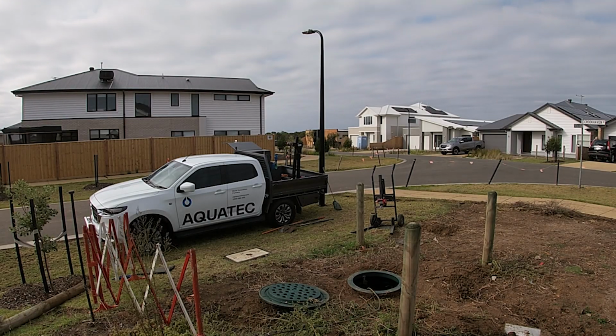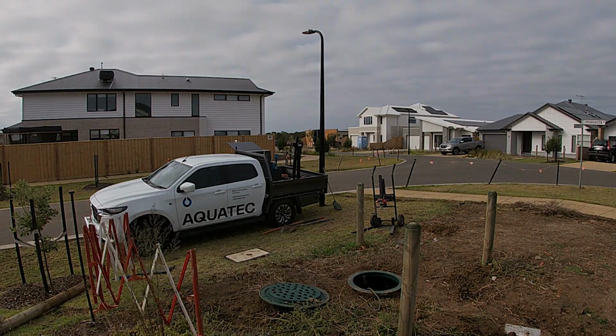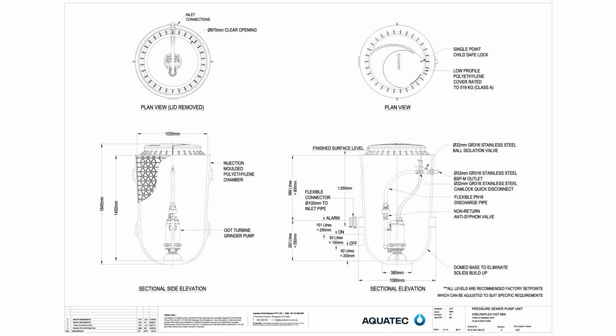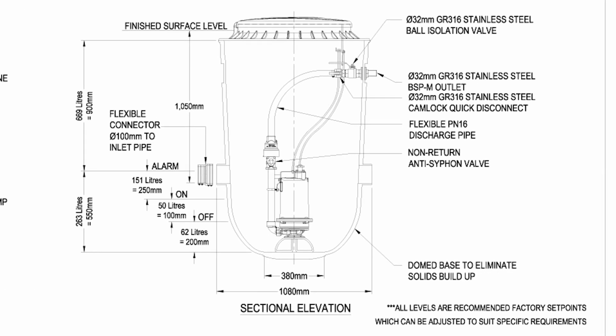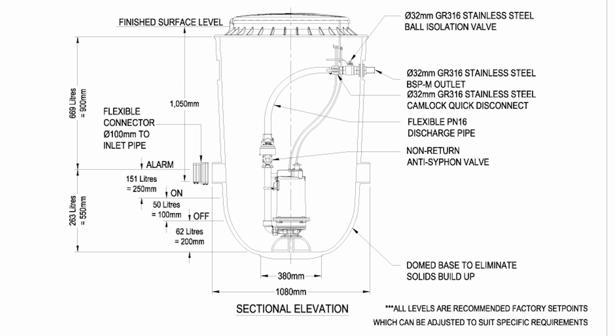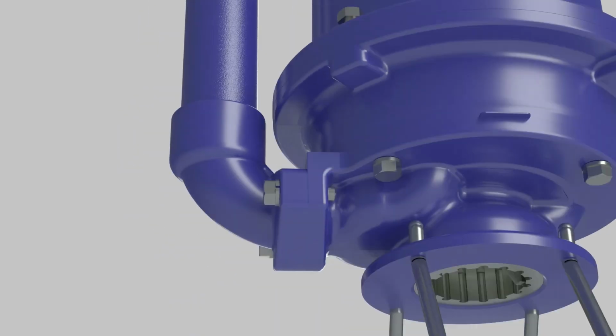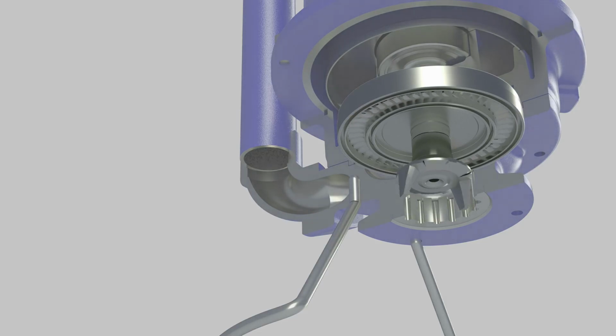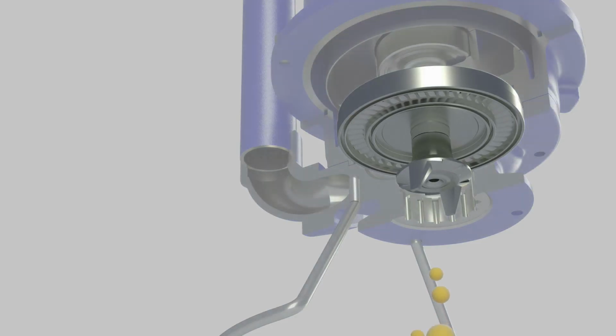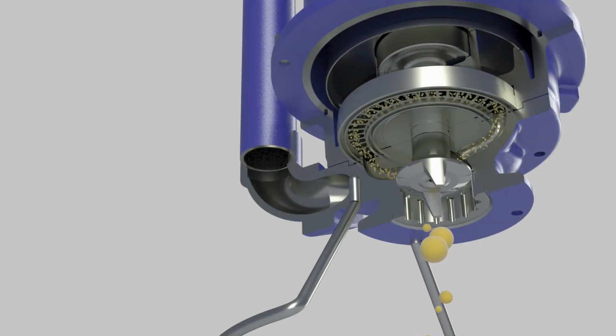Continue to pump the system out until it gets to its off level. The off level should be verified back to the system drawings showing the operational levels. Typically, this is between 200 and 250 millimeters of liquid left in the bottom of the well. In any case, it should always cover the wet end of the pump. It doesn't necessarily matter about the motor being exposed. These are oil-cooled pumps and designed to operate this way.